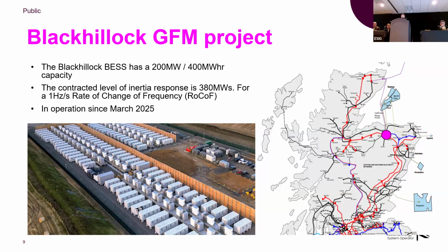The procurement was done a couple of years ago, and this plant was commissioned in March this year. It's about a 200 megawatt battery, and they are contracted to provide 380 megawatt seconds for the inertial response, and they're also providing short circuit level support to the system as well.